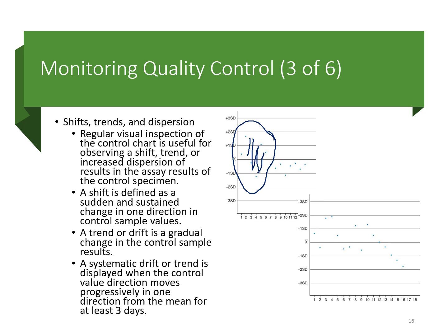Versus a trend, when we look at this data down here at the bottom, you can see this little trend where all of a sudden each day you run it, it's going down more and more and more. Once you start seeing some of these things, it may flag you that you need to look at something. When we talk about a systemic drift or trend, they're progressively moving in the same direction. So this second chart here demonstrates more of a trend downward. This flags us that we need to look at something.